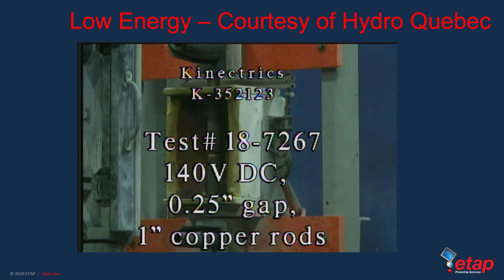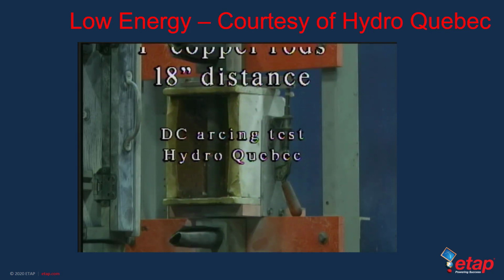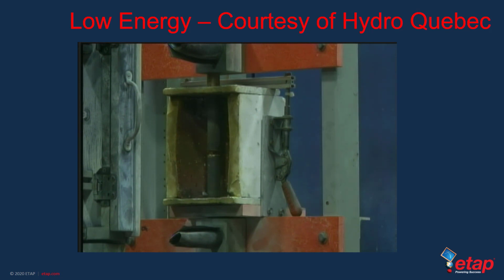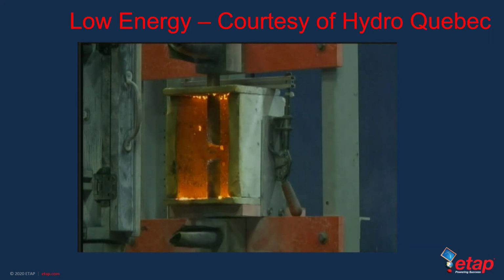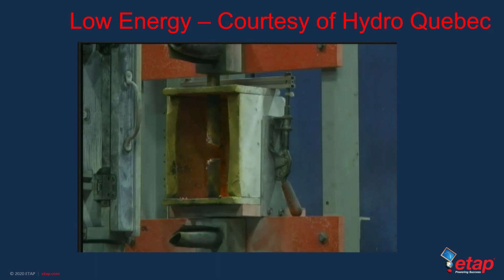The current is high enough to generate immediate shrapnel, molten metal and plasma clouds, and other effects like high ionization of the molecules in the air around this arc. The voltage is lower than that of the previous photovoltaic system by at least a factor of 3, being around 140 volts DC. So, in conclusion, it is not the voltage that has a significant impact, but the actual amount of short circuit current and the gap of this particular test event. As we can see, the gap has grown from 6 millimeters to over an inch because of the arc erosion caused by the shrapnel and the ionization of the conductor material.